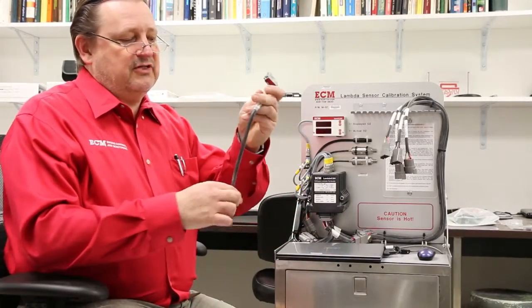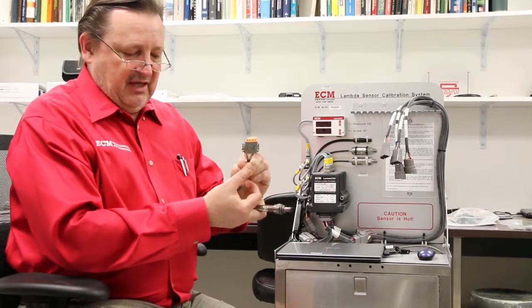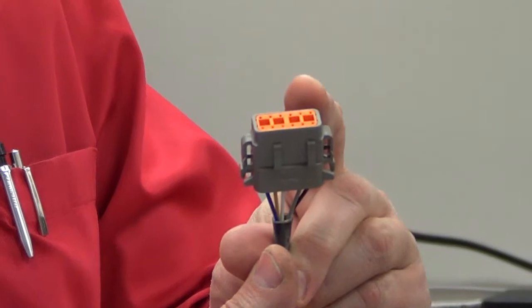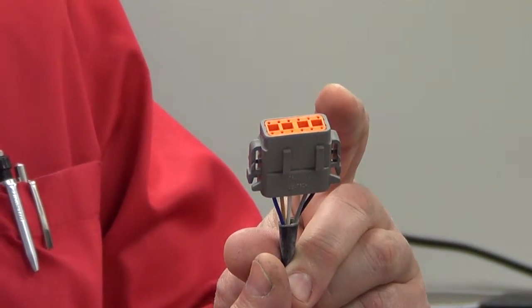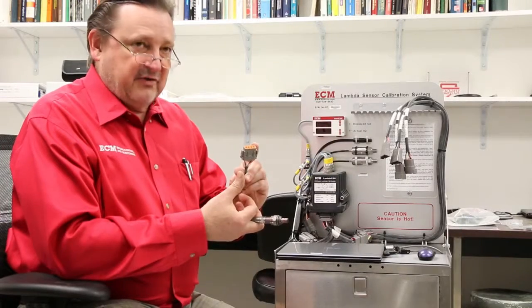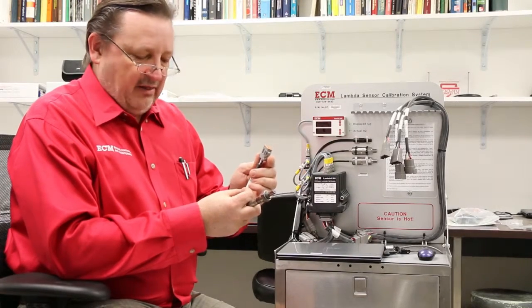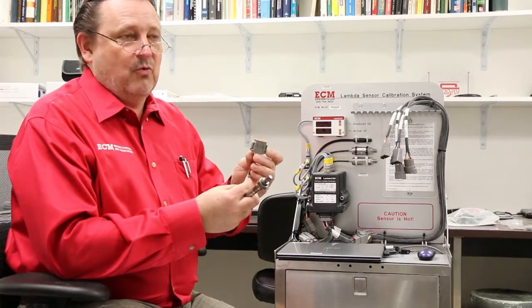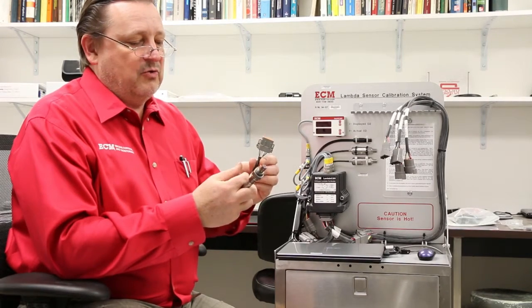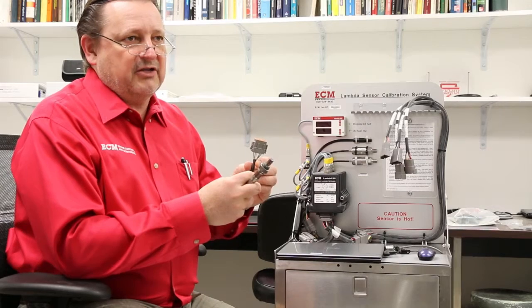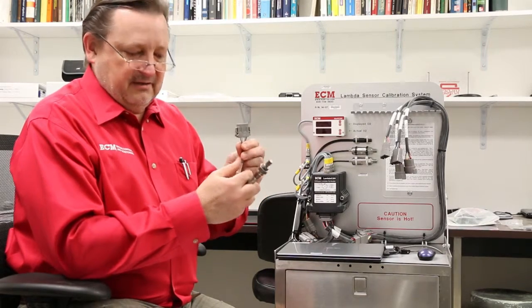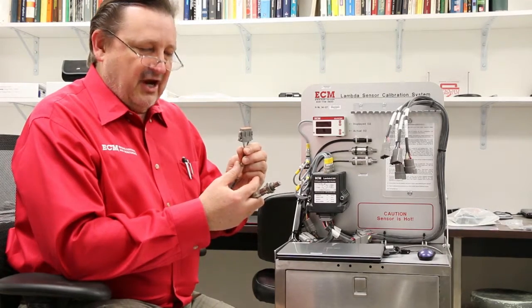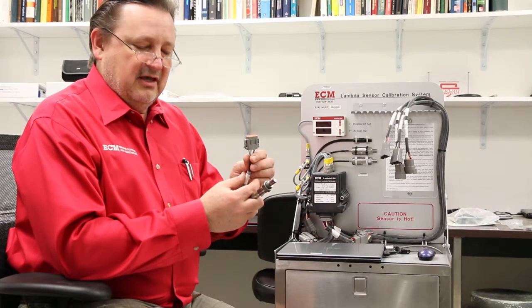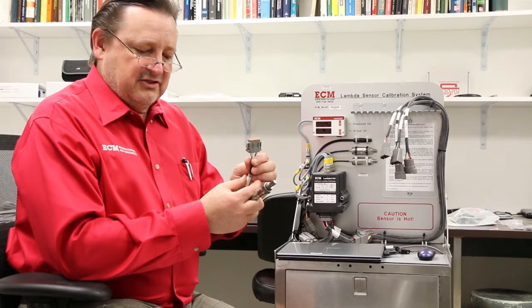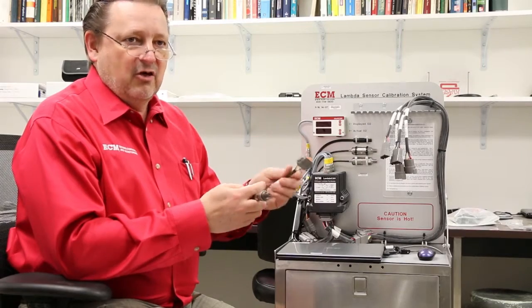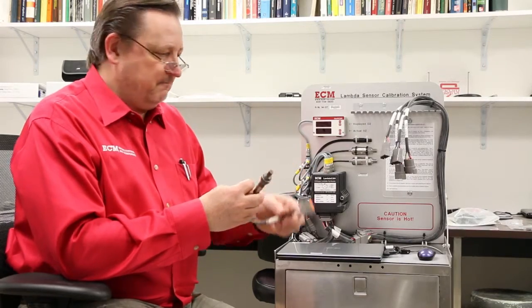The sensors used in these devices have a memory chip in this connector. Factory calibration and user cal is stored in here. So once you do this calibration, you can send this sensor to a location and your calibration will be retained. Sensor calibration with this device allows you to maintain consistency and traceability through a large test facility.